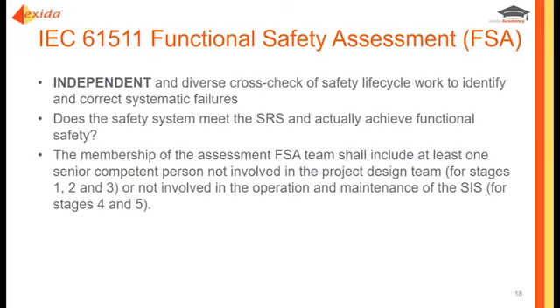The purpose is to look and see whether the SIS, Safety Instrumented System, meets the safety requirements specification and actually achieves functional safety. This is very important - we have to make sure that the as-designed and installed SIS with its SIFs will actually achieve what we want in terms of risk reduction and providing the necessary functional safety.